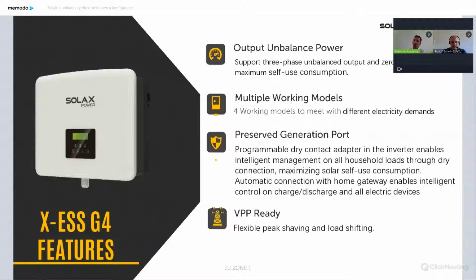So, is it possible to use SolaX for zero power to the grid, like power limitation, if it's necessary? That's also possible. So together with the energy meter, the installers can activate, for example, the zero export function, or an export function with another amount of watts allowed to go to the grid. But of course, this amount can also be zero, like a zero export function. It can be activated in the settings of the inverter.